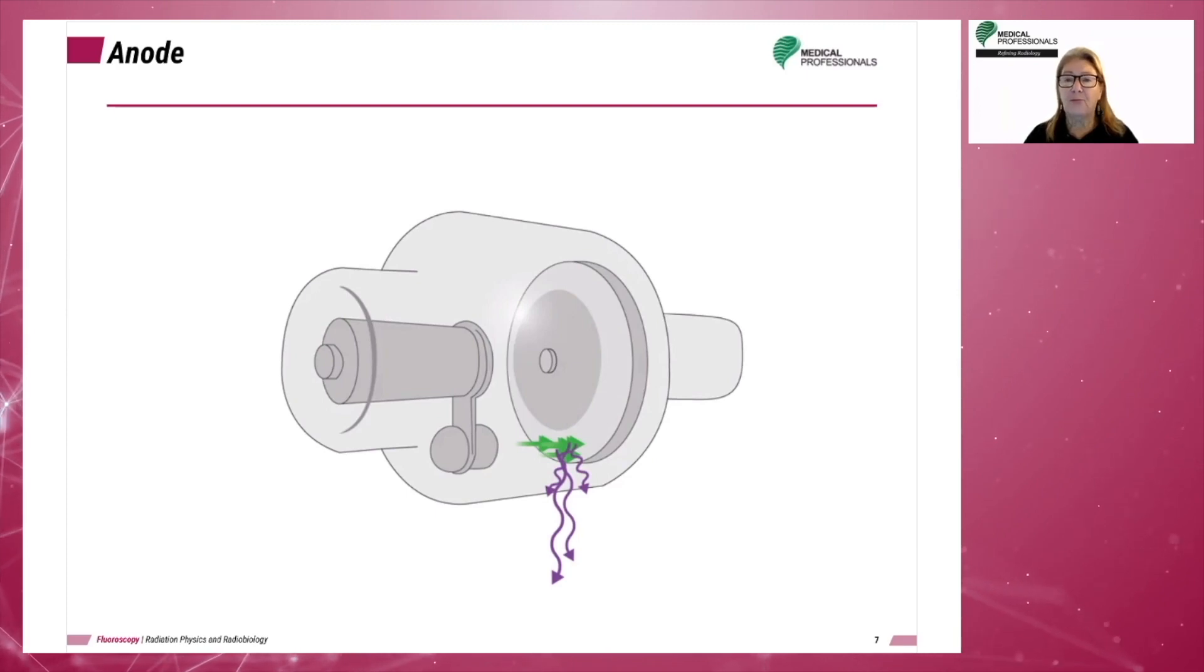The high melting point is essential because of the amount of heat generated during X-ray production. And the high atomic number is essential so that the electrons produce X-ray photons in the range required for diagnostic imaging. Now we have an electron cloud boiling off at the filament, being held in place by the focusing cup at the negative end of the tube, and the rotating tungsten target at the positive end of the tube.